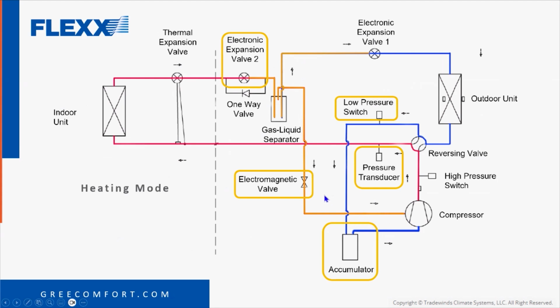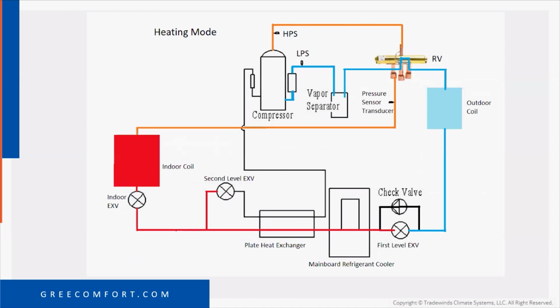So, and now this valve, I've said this before, it depends on how cold, all the other conditions from the thermistors, all the data that the outdoor board receives as to how long and at what temperatures that electromagnetic valve is actually opening. So this is that gas liquid separator that I was talking about that we got rid of going to the R32 equipment. Because as you can see, you see the gas liquid separator there. When I go back here, you no longer have that anymore.